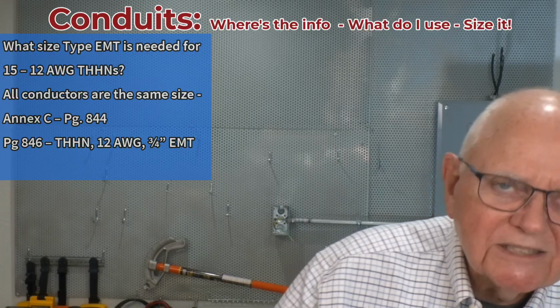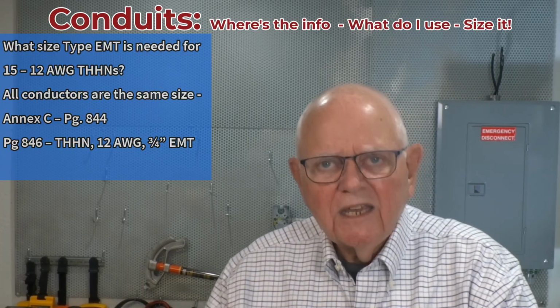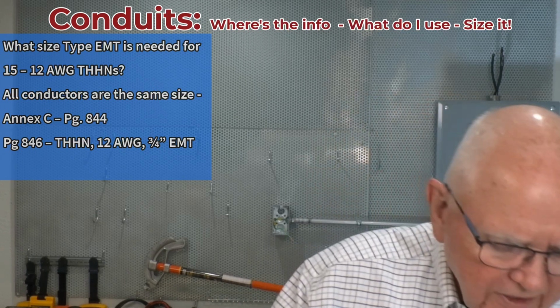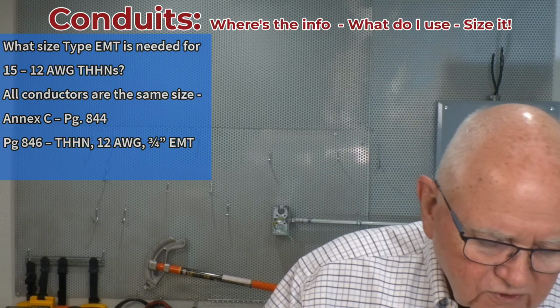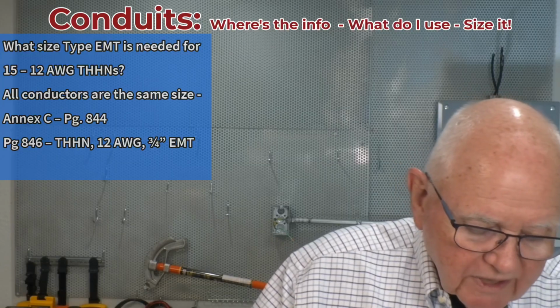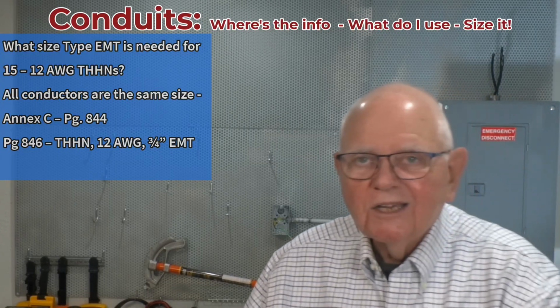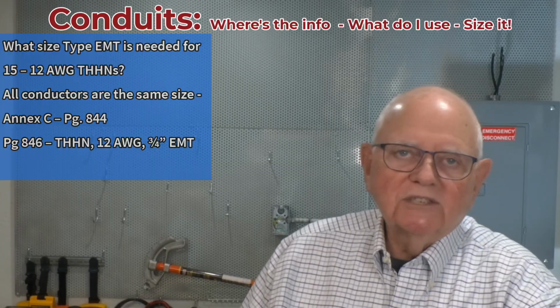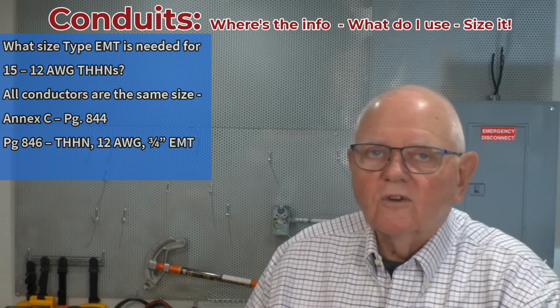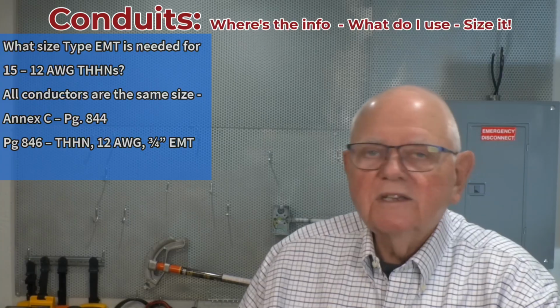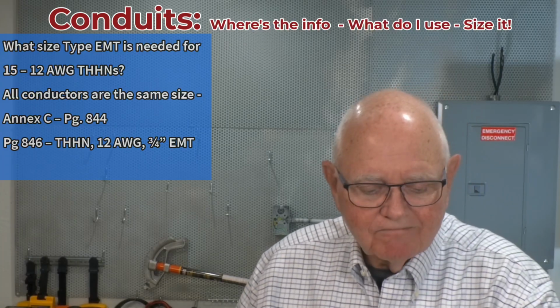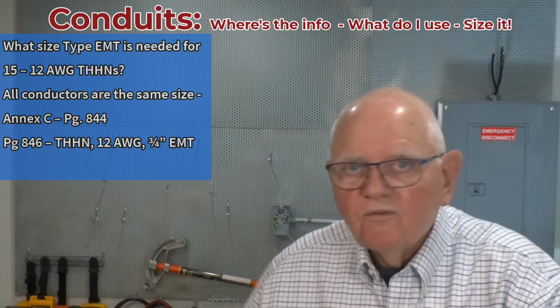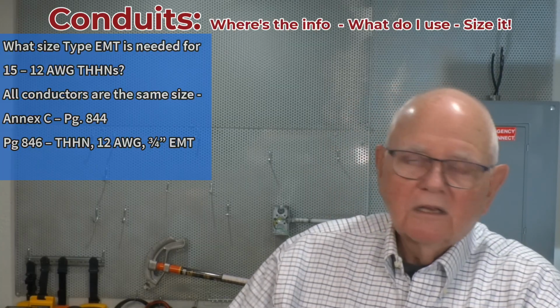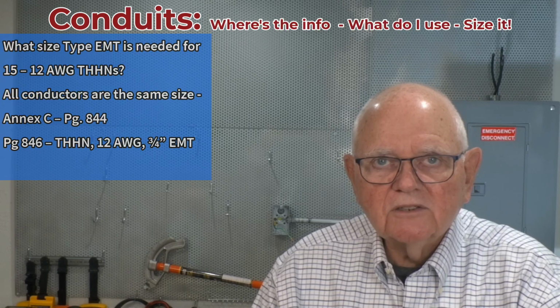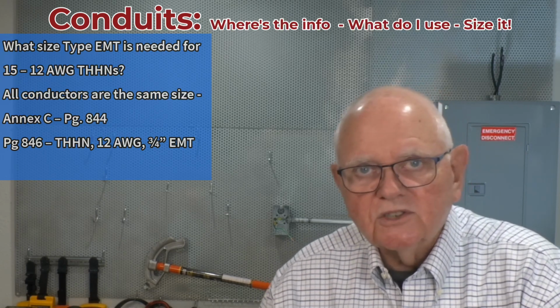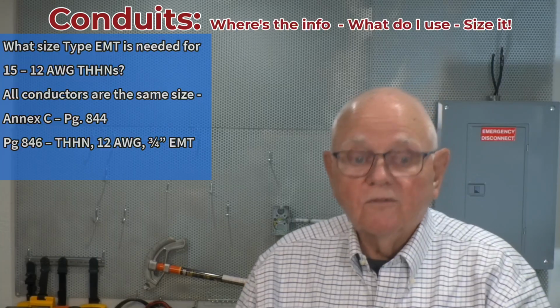And then I read over, and I said I needed 15 of them in an EMT. What size EMT? Well, I read over. Number 9 could go in a trade size 1/2. That wouldn't work. But it says that a trade size 3/4, I could put 16 of those number 12 THHNs in there. So that 3/4 would work for my 15 12AWG THHN conductors then. So Informative Annex C: find a particular raceway that applies.